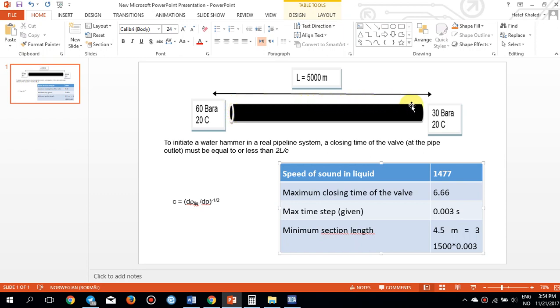The pressure wave travels all the way back to the upstream location and then returns to the valve. The travel distance is 2L at speed C. If the valve is not closed by the time the pressure wave returns, the wave escapes through the outlet and you will not see the water hammer phenomenon. So the closing time must be equal to or less than 2L over C.